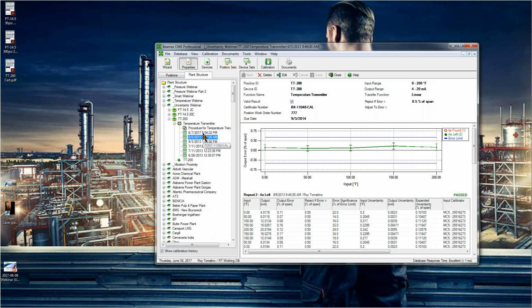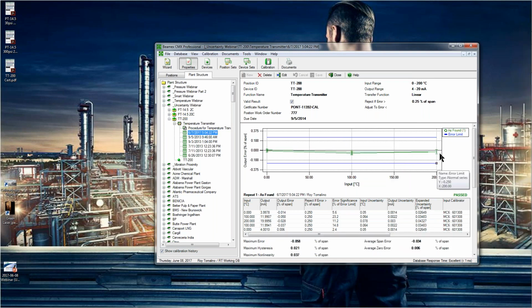And now you're looking at it. Let me show you on the high end, on the 200 degrees. You see the test point, the little dot. Then you see lines above and below that dot. This is the uncertainty shown in a visual representation. So I think this is the easiest way to talk about uncertainty. Normally when you talk about uncertainty, you have a guy with one of those propeller hats talking about all these details, but 5 seconds later, your eyes are completely glossed over and you have no idea what they even said. But if you have a visual representation, and at least I'm visual, it's easier for me to understand. So this is a visual representation of the uncertainty at every single test point.